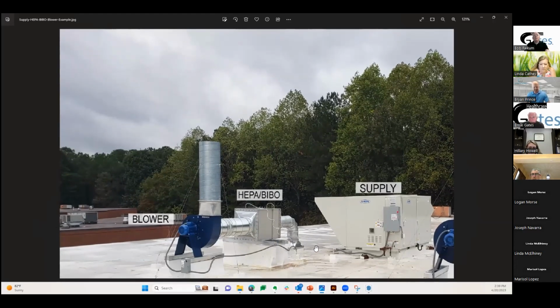You see where the supply is, and where the hood is discharging, and it has to be a certain height in the air, which that appears to be. You also have to have it 20 feet away from the source. In other words, if you slid that hood down, that's not compliant. And it's happened, it was a major hospital and they had done that. So be aware that there are local codes regarding biohazard spacing requirements. Just throwing that in in case you run into it, because unfortunately we did.